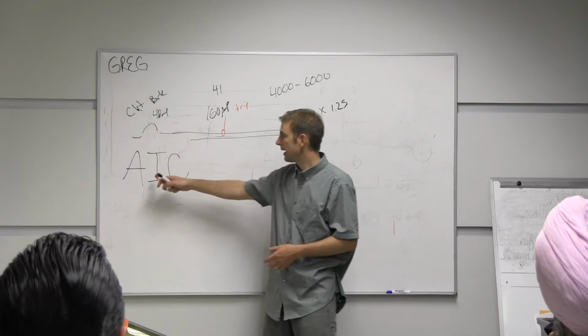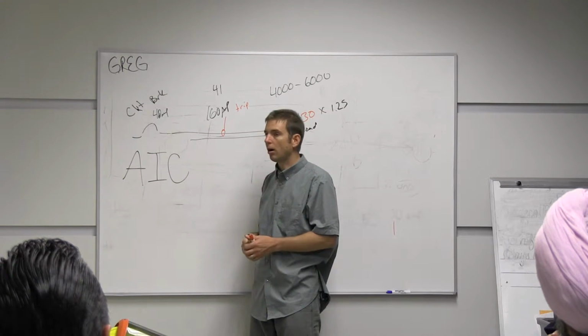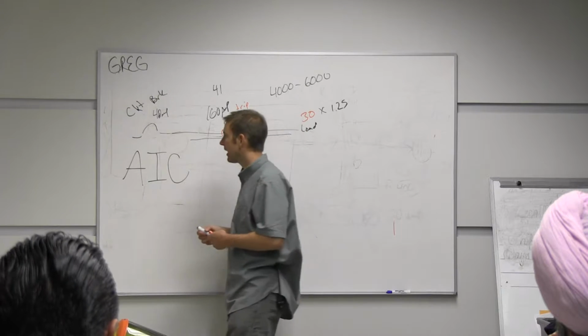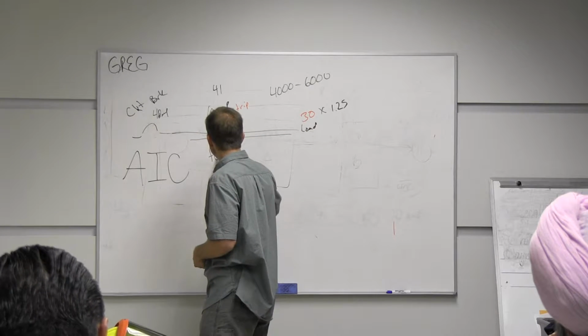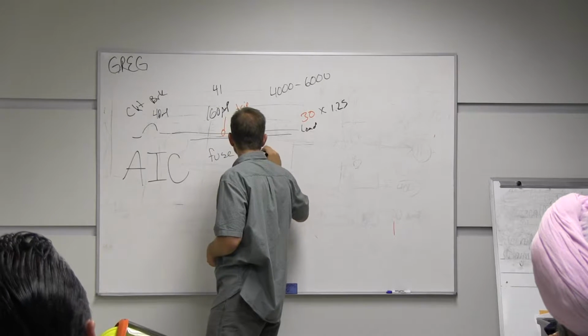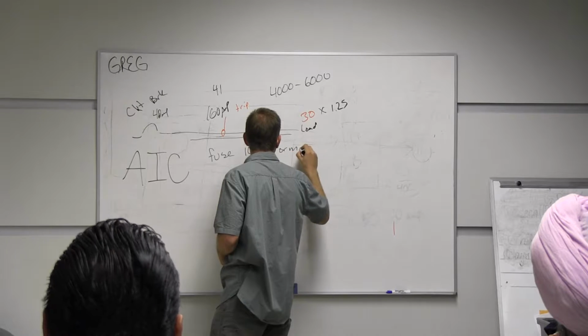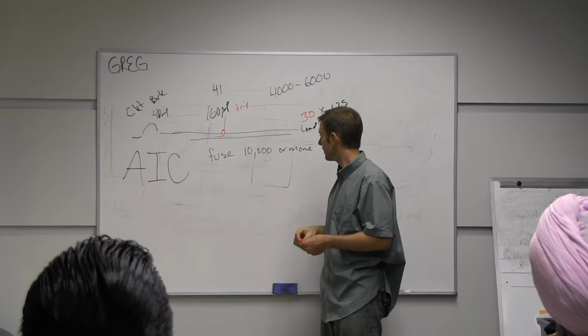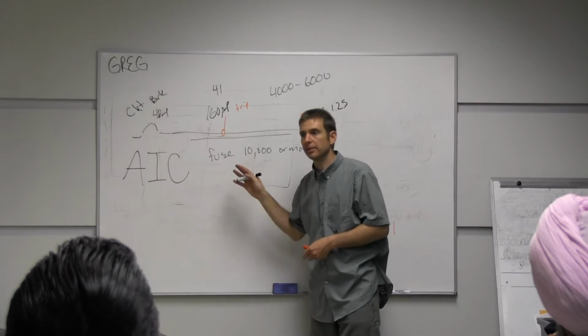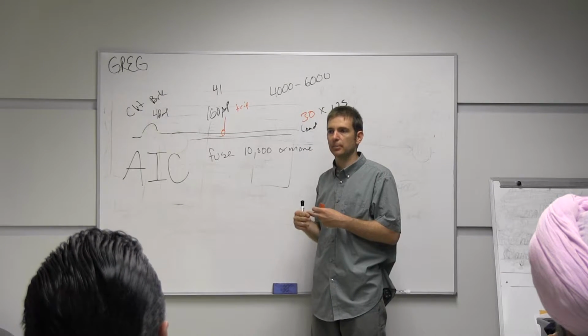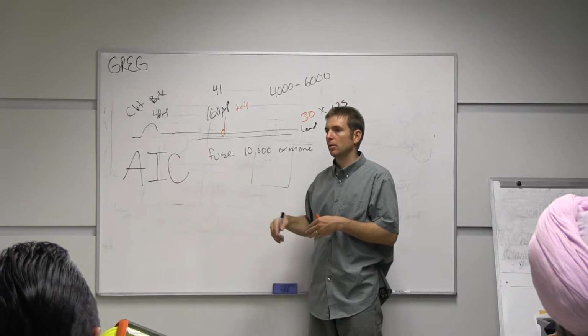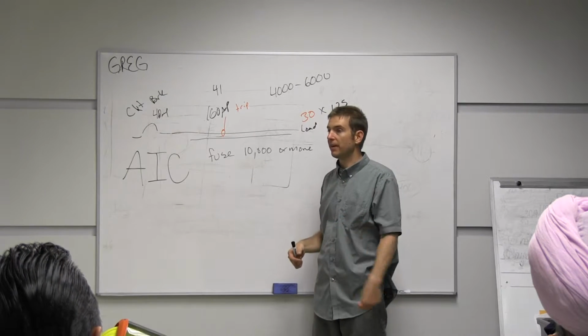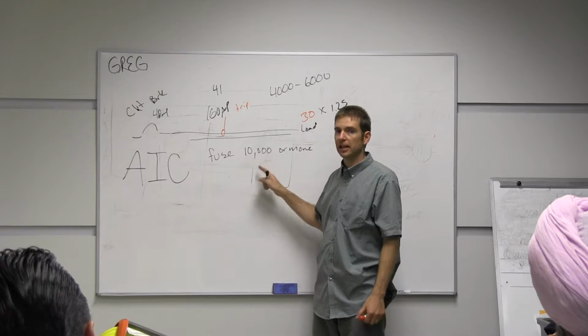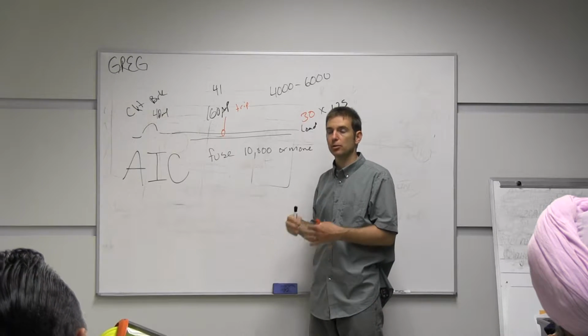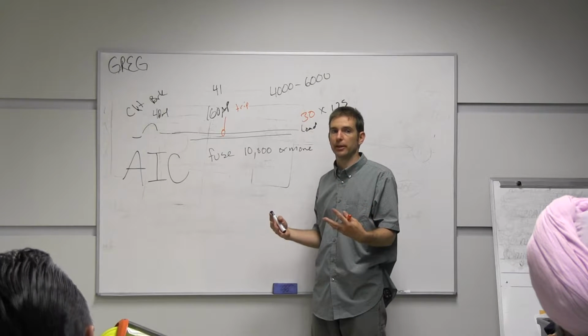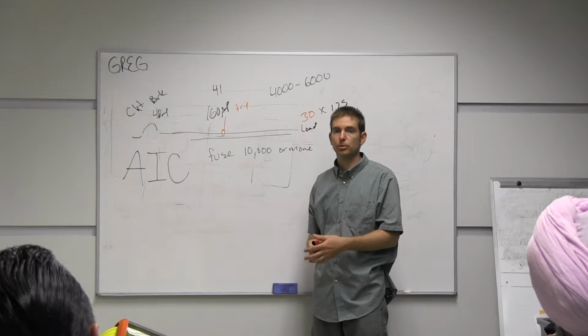So what happens is at AIC, we have amps interrupting capacity. So all fuses have an AIC of 10,000 or more. So all fuses are manufactured to accommodate 10,000 amps of inrush capacity or more than that. Now that doesn't mean that my 5 amp fuse won't burn at 10,000 amps. It just means that at 10,000 amps through that for a short amount of time, it's not going to explode. It's not going to obliterate. So it's not going to do what maybe my tool did.